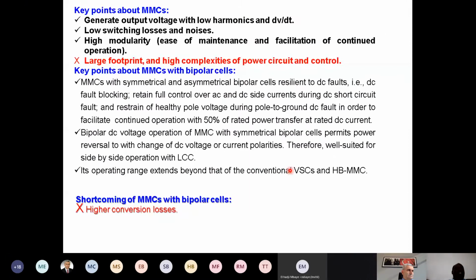Just to capture the key point here, the MMC generates output voltage with low harmonics and dV by dt. This is important because this has implication on the design of the transformer. So with a large number of cells, you can use a simple transmission transformer, which is cheaper. While if you have fewer cells, you have to use a slightly expensive transformer to be able to cope with the switching action of the IGBT and the stress due to the switching.